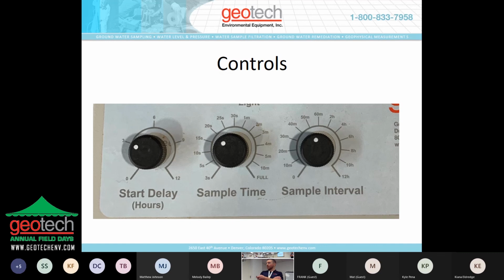and some controls here. So when you deploy these, for example, if you wanted to collect a portion of your sample at an hourly interval, this is where you would set that. The sample time is how long the unit's going to pump each interval, and then the start delay. So you configure this, you put it in the cooler, in our case, right? You may need a little bit of time to get it deployed before it starts collecting a sample, or it's not going to be in the water yet. So that's what the start delay is.